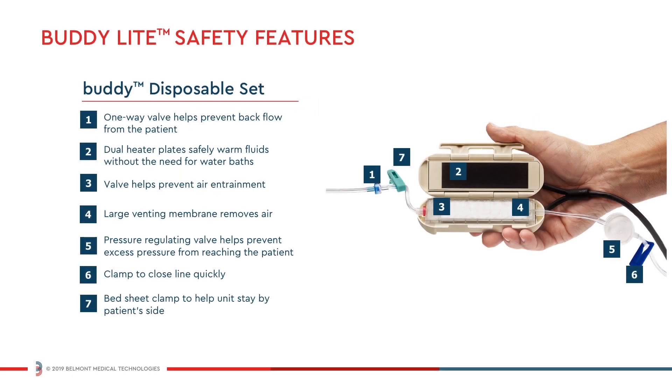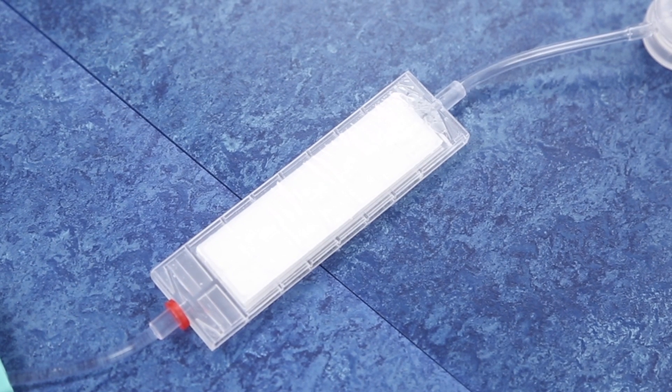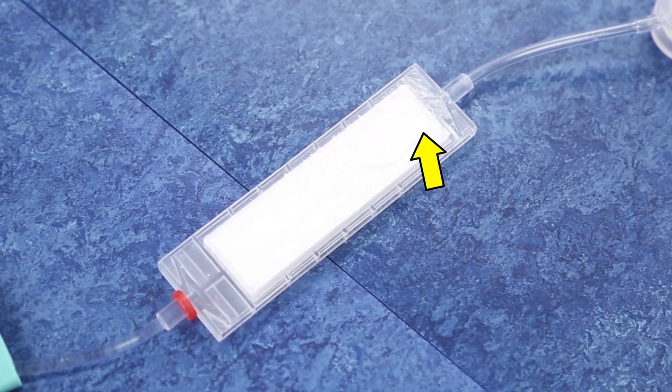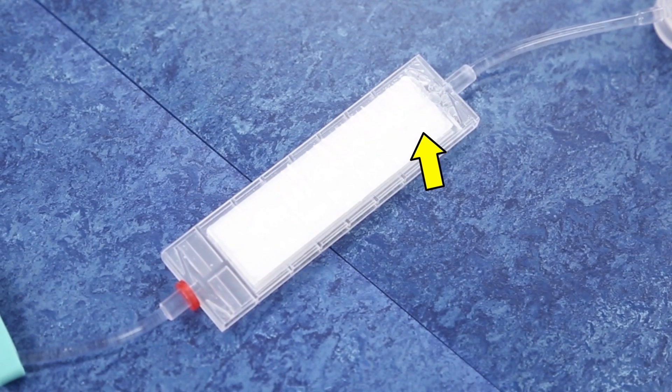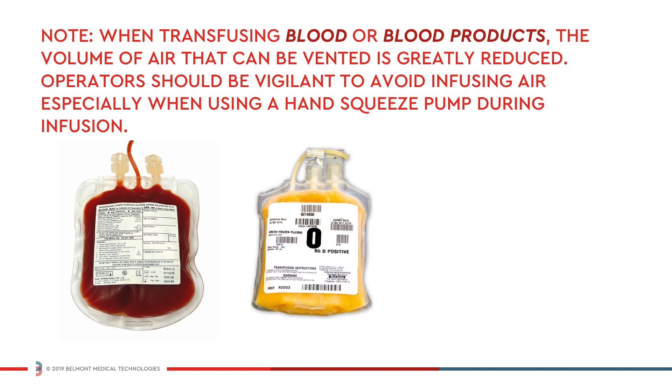The buddy disposable set is equipped with multiple safety features that can help protect the patient from unsafe operating conditions. As crystalloid solution travels through the disposable set, the microporous membrane located within the disposable automatically vents air. When transfusing blood or blood products, the volume of air that can be vented is greatly reduced. Operators should be vigilant to avoid infusing air, especially when using a hand squeeze pump during infusion.